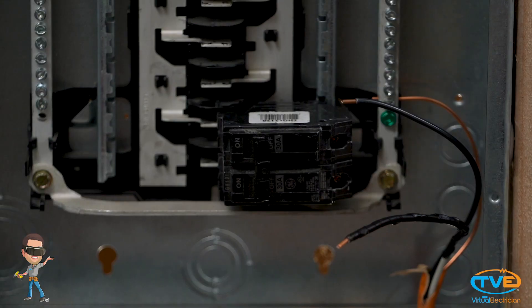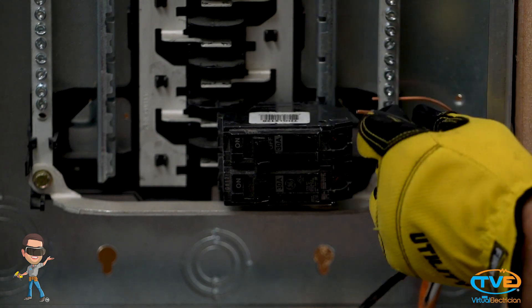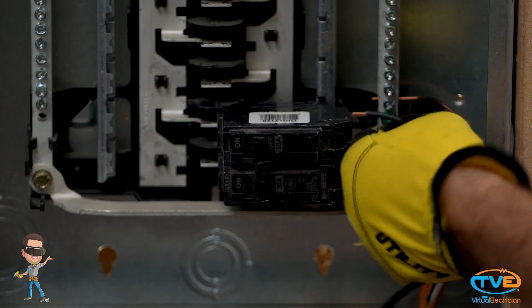Now install each circuit. Land the grounds on the ground bar, the neutrals on the neutral bar, and the hot wires on the breaker. Snap the breakers into place. Make sure the green bonding screw in the panel is tightened down.